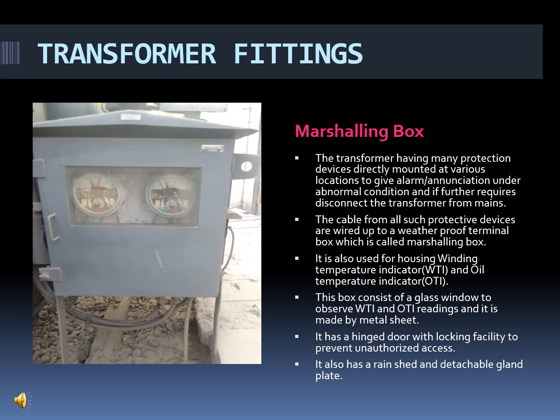In many transformers, you can see a box which I have enclosed in the image. This box is known as a marshalling box. We will discuss the uses of this box in this slide. The transformer has many protection devices which are directly mounted at various locations on the transformer, for example the Buchholz relay, pressure relief valve, winding temperature indicator, oil temperature indicator and many other protection devices located on some side of the transformer. The cables from all such protective devices are wired up to this terminal box. This terminal box is a weatherproof terminal box and it is called a marshalling box.